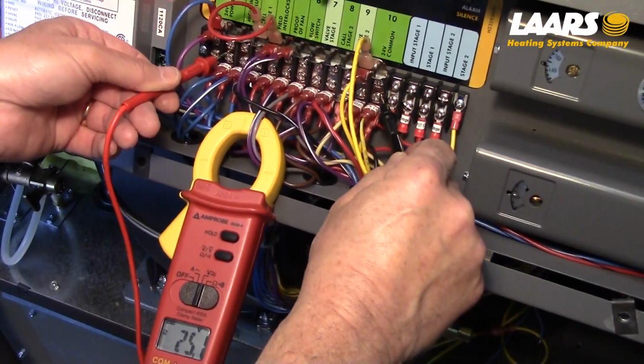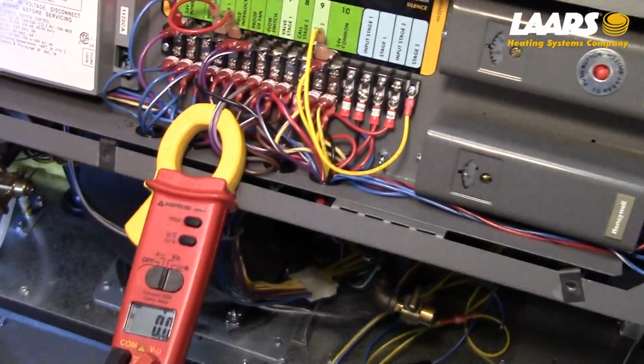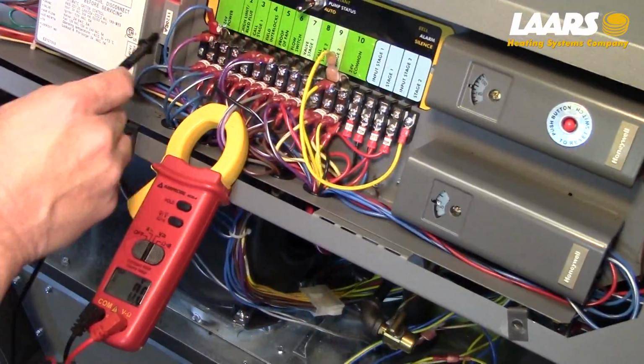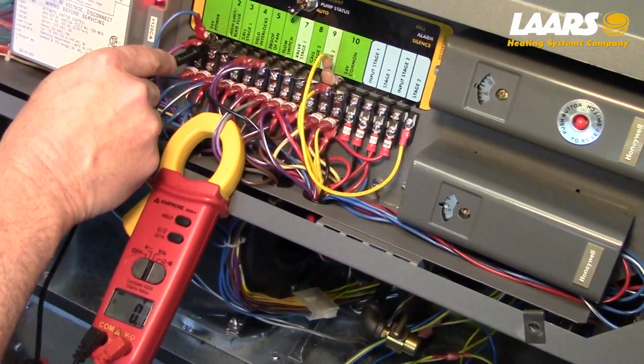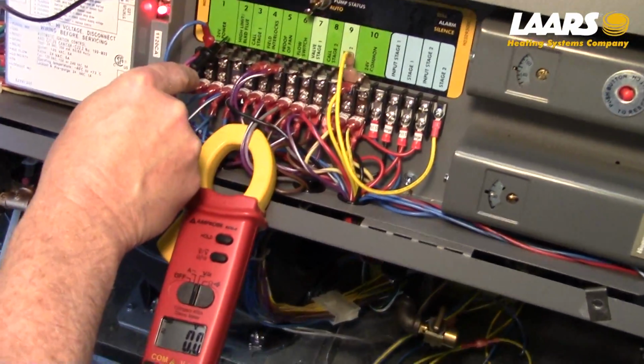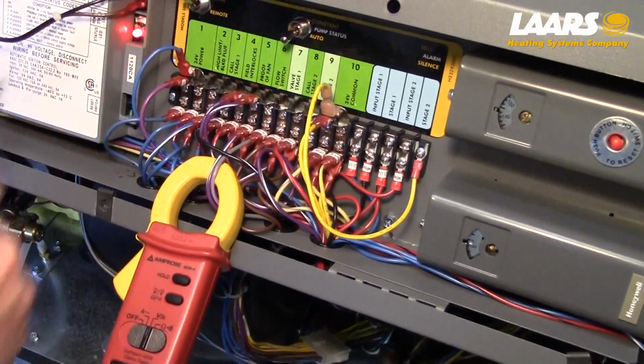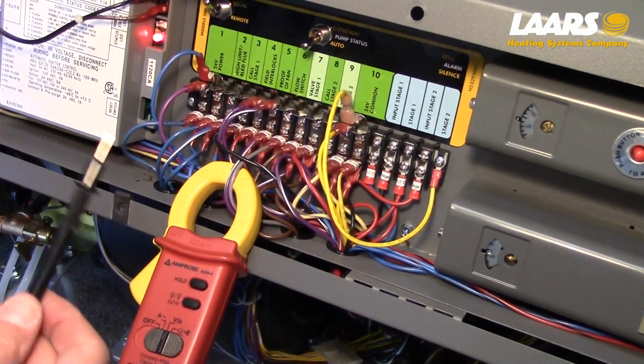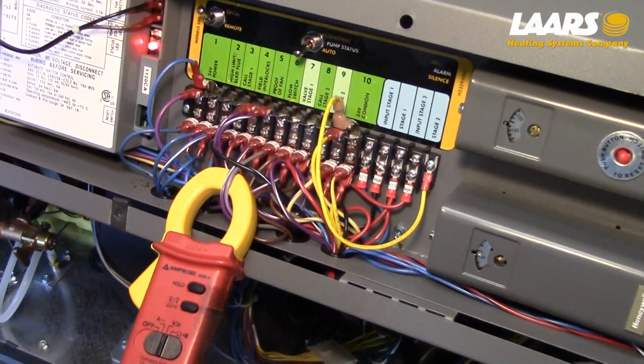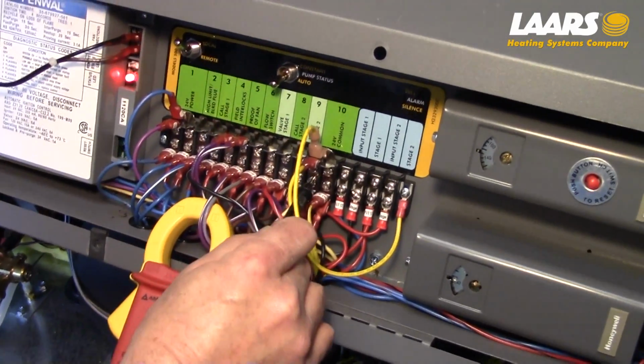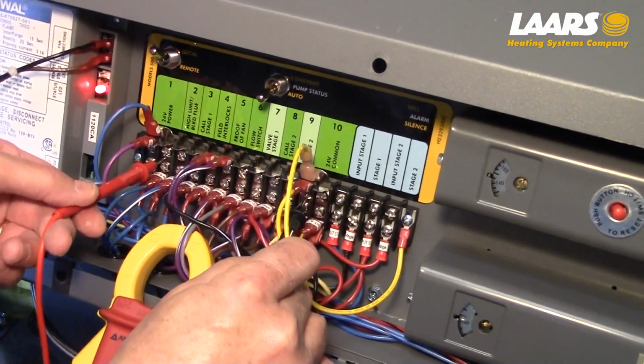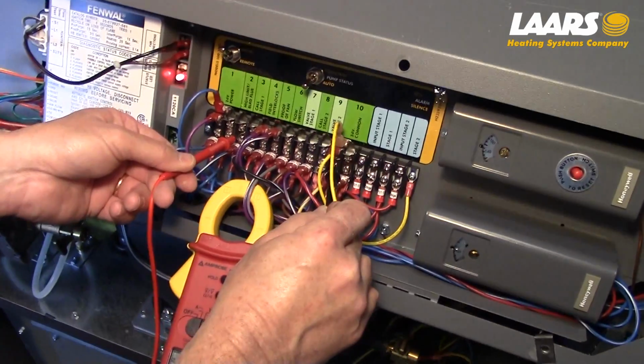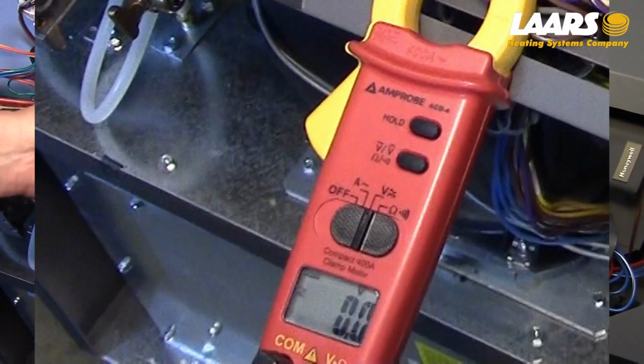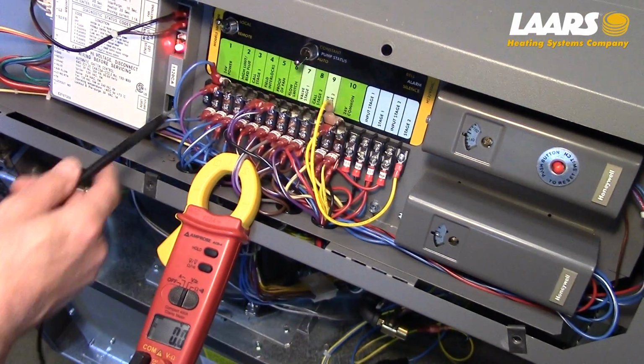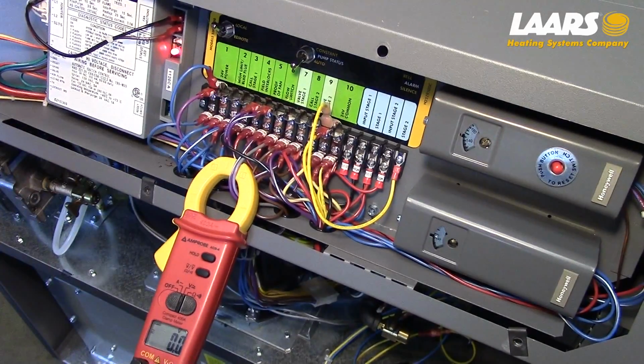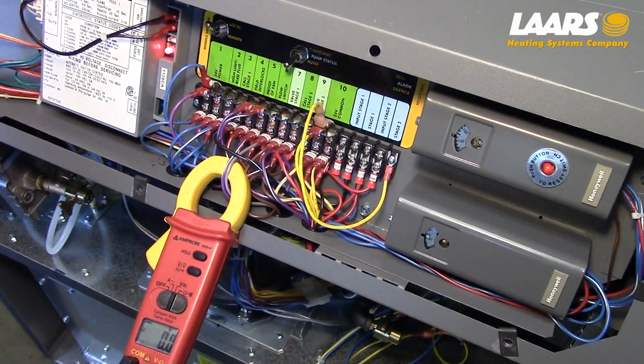So now I'm very simply just going to walk through this terminal strip. So here you can see terminal 2 reads high limit blocked flue. Alright, so that's going to be my next test. There's also something else in the circuit that I'll show you in a minute. So 24 volt common, come over here, I got my power, next terminal over, terminal 2, I do not have voltage.